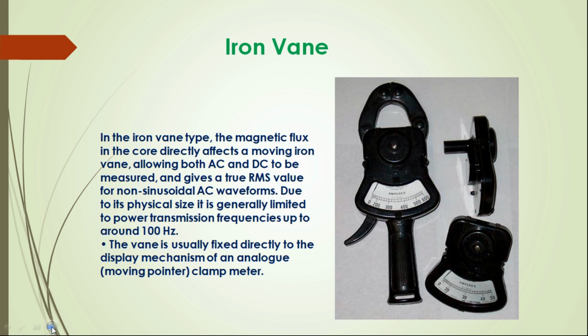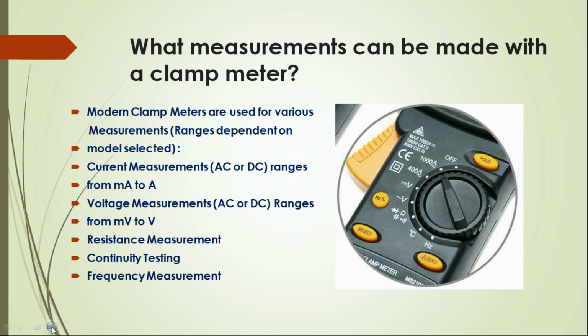Now, what measurements can be made with a clamp meter? Modern clamp meters are used for various measurements. Number 1, current measurements, AC or DC, from milliampere to ampere. Voltage measurement, AC or DC or both, measured from millivolt to volt. Resistance measurement, continuity testing, and frequency measurement.